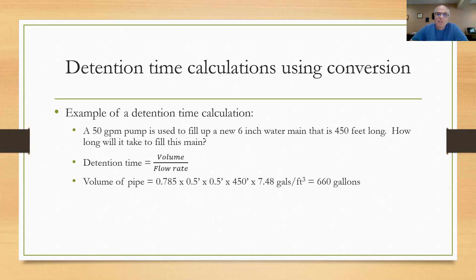What I've chosen to do is to take the diameter of 6 inches divided by 12, I get a half a foot diameter. I'm doing 0.785 times a half a foot squared times the 450 foot length. That will give me cubic feet. So I have to multiply by 7.48 gallons per cubic feet. Now I've calculated my volume of 660 gallons. I can put that into the formula because the flow rate that they gave me was 50 gallons per minute. And I see that the detention time is going to be 660 gallons divided by the 50 gallons per minute, or about 13.2 minutes.